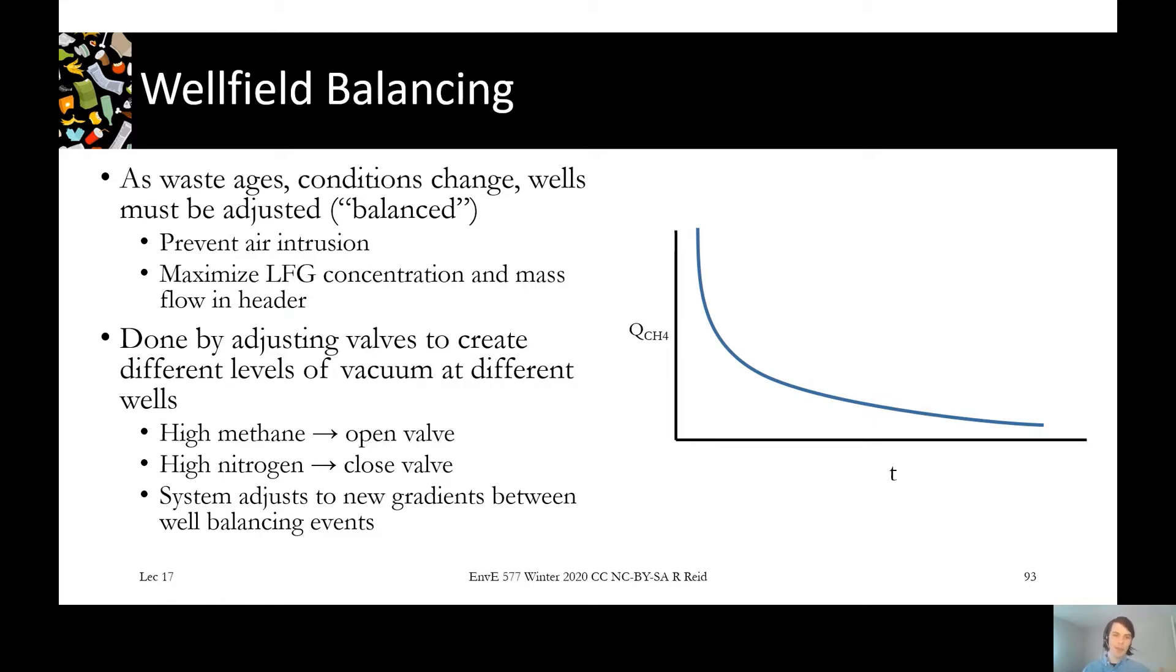As you're balancing, what you'd be doing is going to each well. If you see really high methane like 60% and no oxygen, then you know that you're getting 100% landfill gas, you're not pulling in any air from the surface. So you might try opening the valve and getting a little bit more flow in.